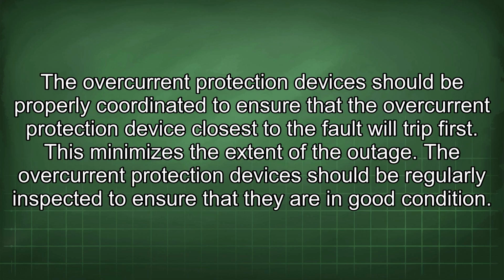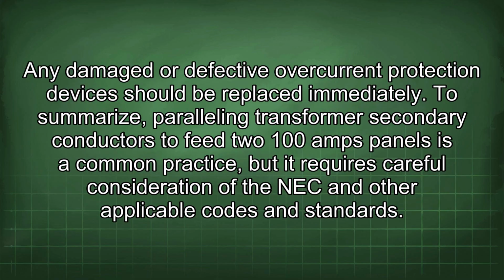The overcurrent protection devices should be properly coordinated to ensure that the overcurrent protection device closest to the fault will trip first. This minimizes the extent of the outage. The overcurrent protection devices should be regularly inspected to ensure that they are in good condition. Any damaged or defective overcurrent protection devices should be replaced immediately.